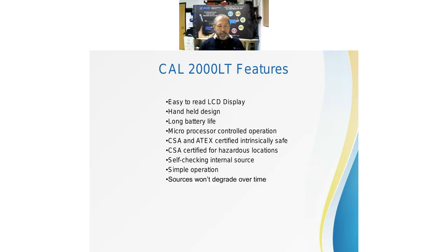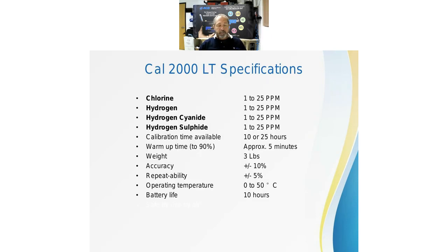So again, microprocessor. This one is also CSA and ATEX certified, and this one's a little less expensive, and it has less features than the Cal 2000. We don't do every gas in this one just because of the complexity of some of the gases, but these are the gases we do. And again, you just order whatever you want. You know, hydrogen cyanide at 8 ppm, half a liter a minute. And so that's how that instrument works.